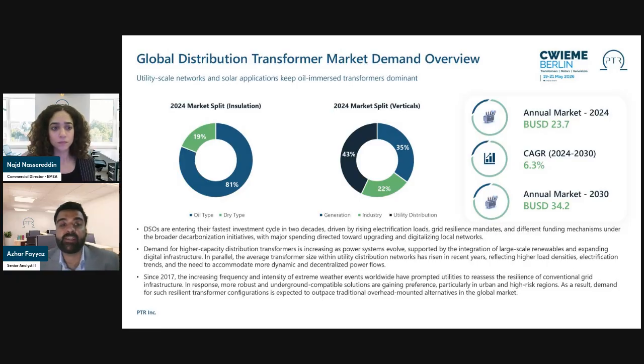Another important trend is grid resilience. Since 2017, extreme weather events have pushed utilities to reconsider overhead mounted configurations, especially in high-risk urban zones. So now they are undergrounding their existing distribution networks, shifting from pole-mounted to pad-mounted distribution transformers. So what we are seeing is a growing preference for underground-compatible units, more robust configurations, and higher efficiency designs with lower losses.